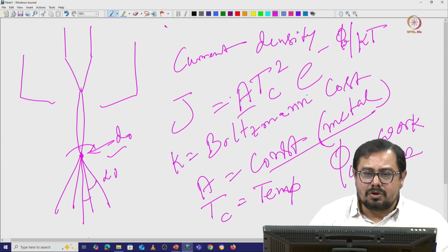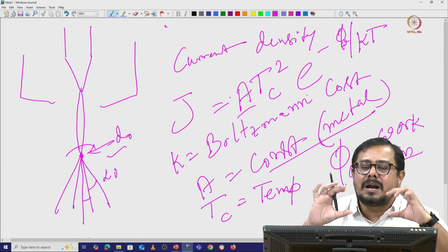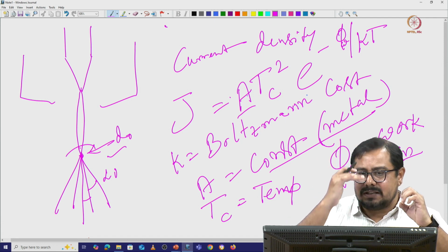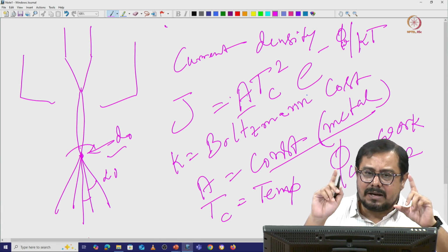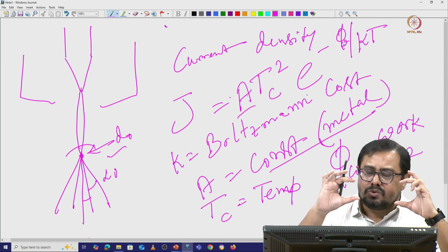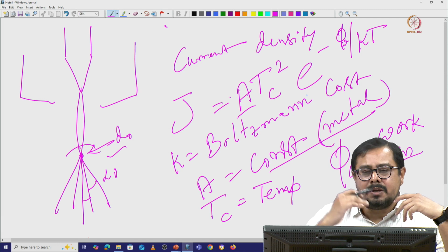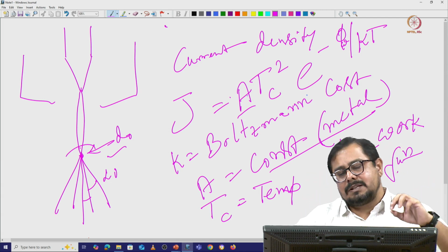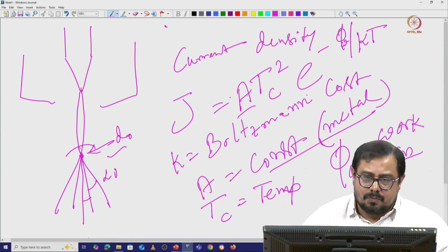Here is one more thing I want to add: for the field emission gun, most of the time we are using two anodes, anode 1 and anode 2, which help to pull out the electrons, and we are using a normal tungsten filament. We are giving heat energy, but at the same time these two anodes are helping us. So, we do not have to apply very strong heat energy to extract the electron, because a very strong electric field is there, helping us to pull out the electron.